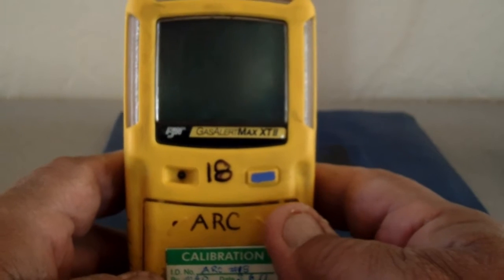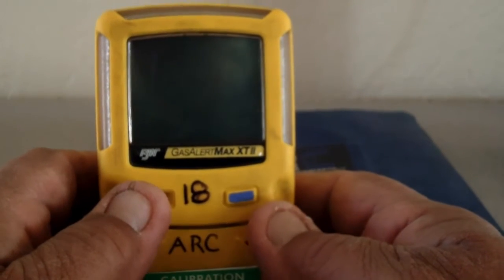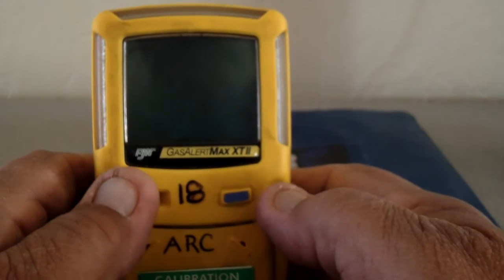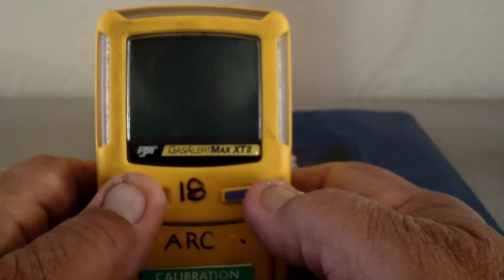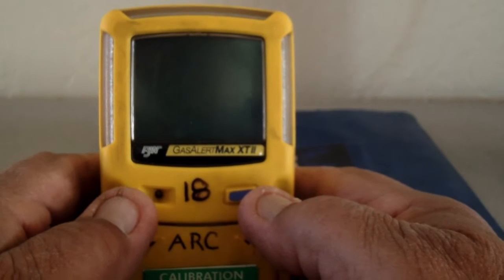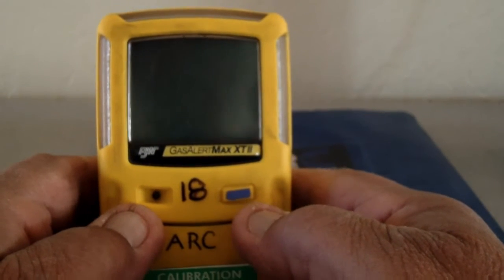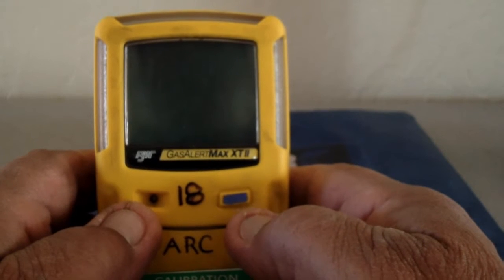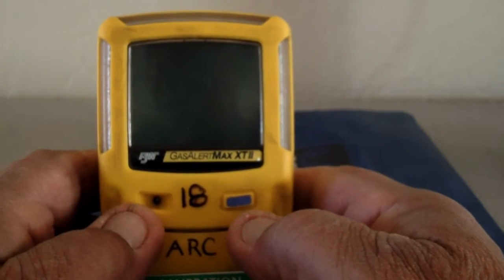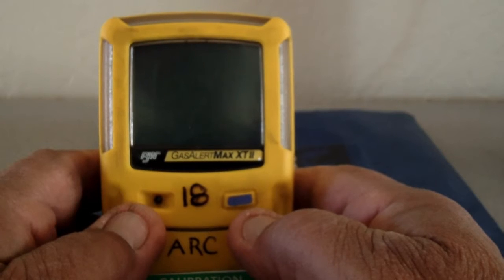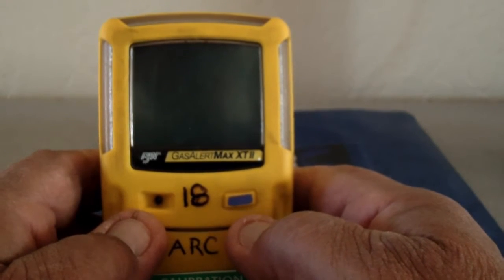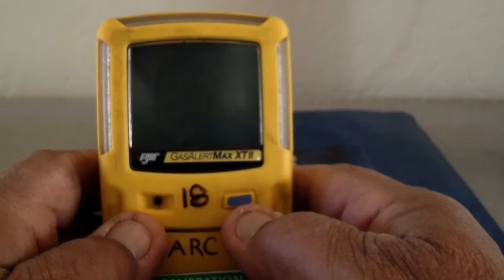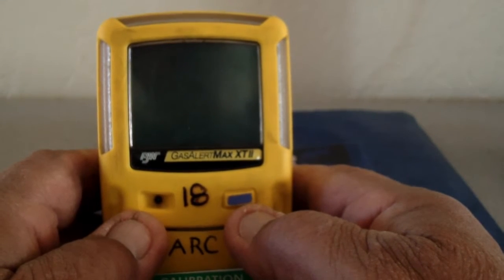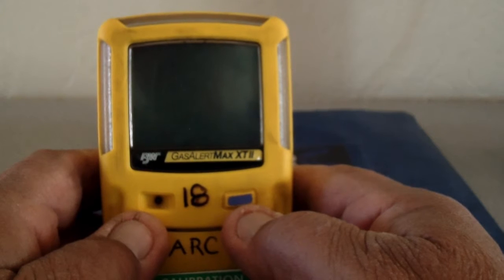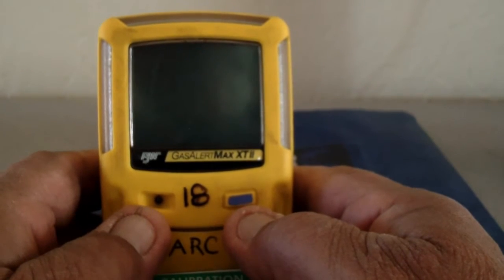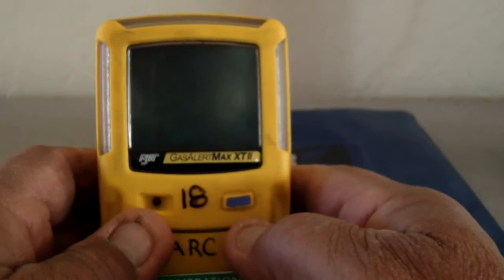The gases that this monitor is set up for are oxygen, LEL or combustibility, hydrogen sulfide, and carbon monoxide, the four required by OSHA for entering and working in confined spaces. It's set up to the acceptable entry conditions. O2 acceptable range is 19.5 to 23.5, 10% LEL calibrated to methane, 10 parts per million H2S, and 35 parts per million for CO. Outside of those limits, it will alarm. So it's kind of a cool meter.